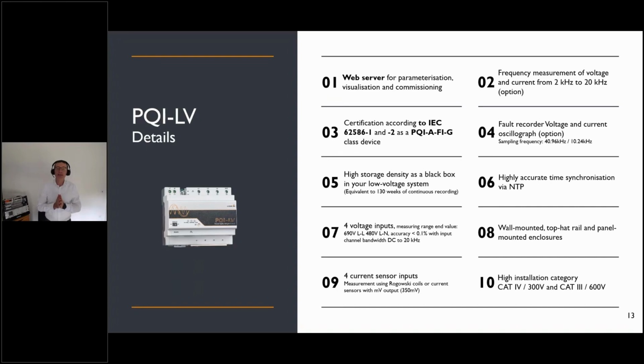The device can be synchronized via NTP, because as we've seen again in Europe with the blackout, there was again a situation where some disturbance fault recorders didn't have the right time, and it's necessary to have the right time to find issues. One big point is also that we have the highest installation category for fixed installed units, so it can be directly connected at the transformer station, being CAT 4 300 volt or CAT 3 600 volt.